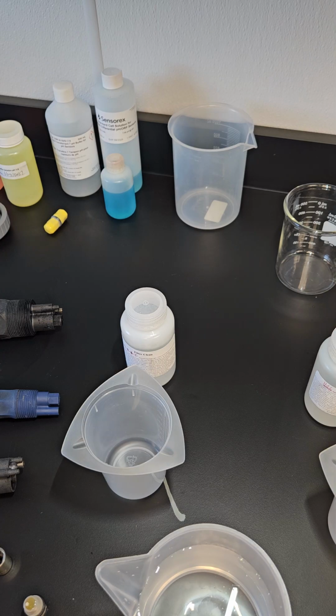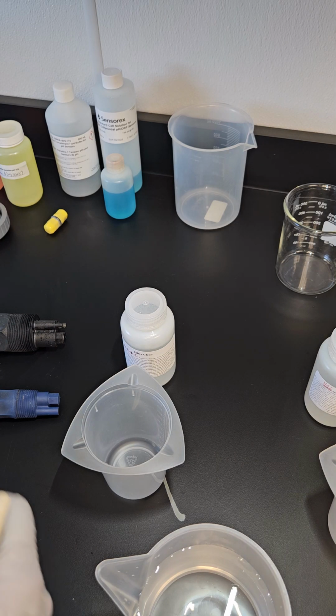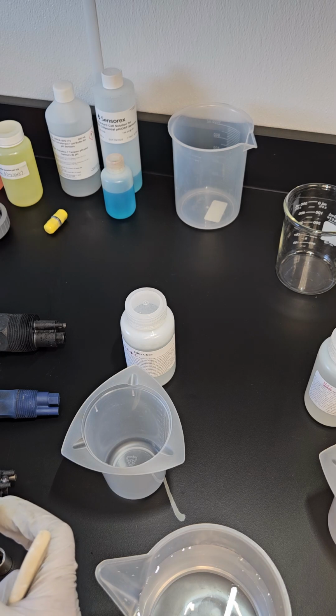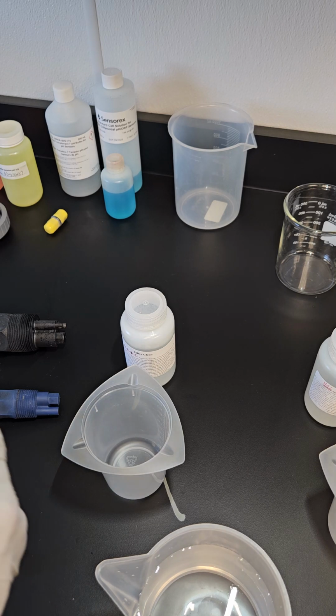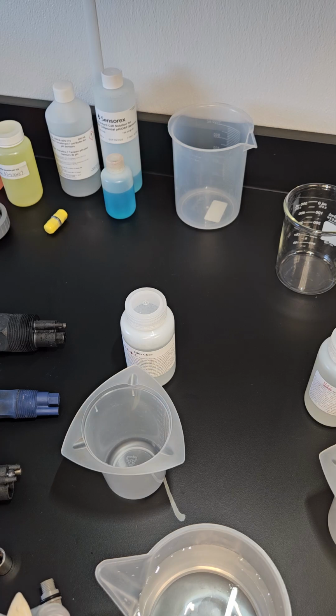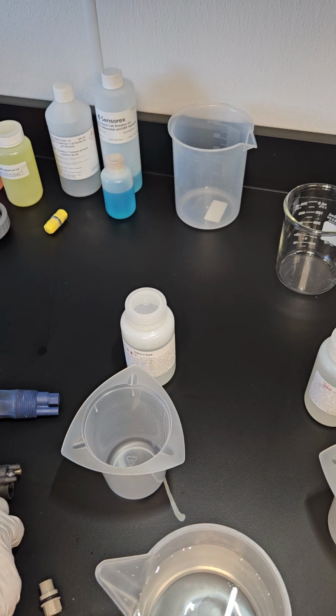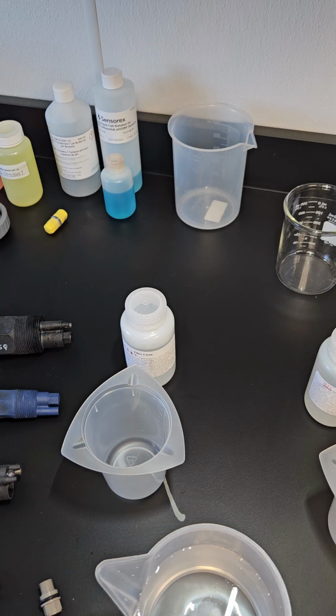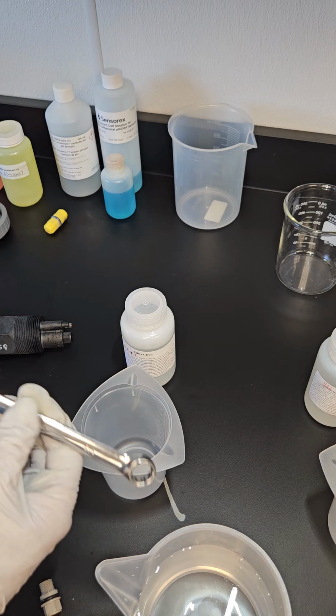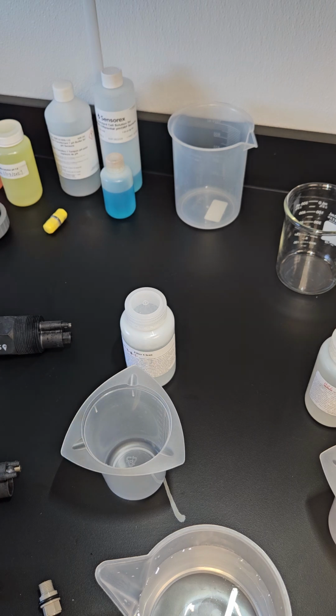So the first thing I want to show you is we have three different types of probes, and they require different types of treatment. There's the Sensorex probe that's like this. It's similar to the Aquametrics probe like this. However, the Aquametrics probe uses a 15 millimeter wrench to remove the salt bridge. The Sensorex uses a 9 millimeter socket to remove the salt bridge. And this 1-inch Aquametrics probe, you must use a 1/2 inch wrench. There's the salt bridge eye.